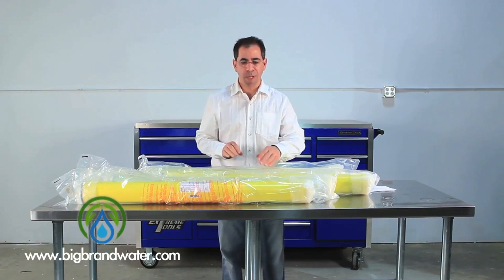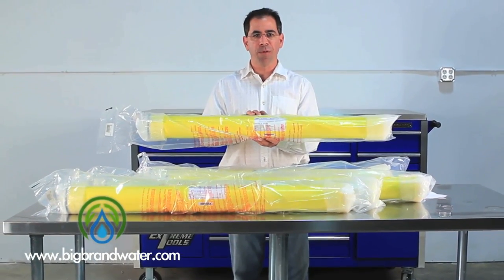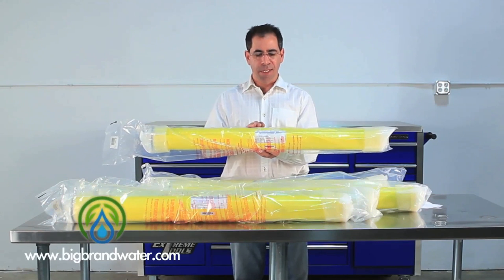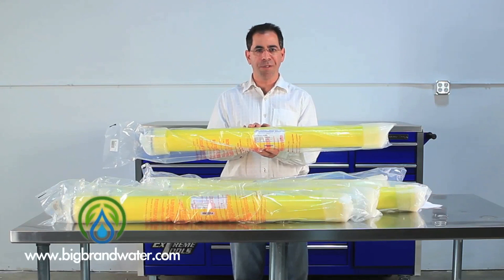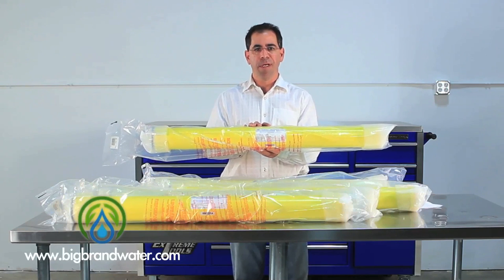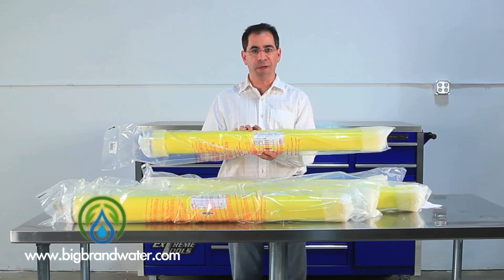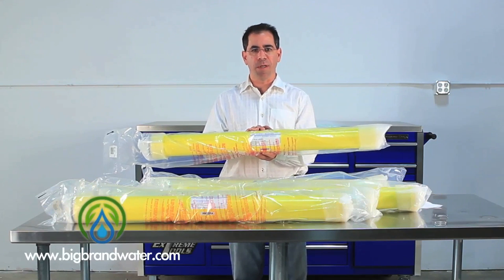We'll move to our next membrane here. This is the XLE4040. This membrane will produce 2,600 gallons per day at 100 psi. This membrane is very popular for the newer, lower energy reverse osmosis systems.